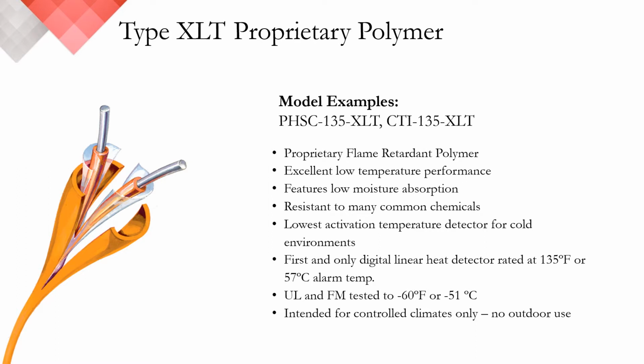While we do offer other products with some well-known industry jacketing materials, such as a PVC or a fluoropolymer, our XLT jackets are manufactured with a proprietary outer jacket material that is extremely soft and pliable. This design feature assures survivability at very low temperatures, as this detector type is UL listed and FM approved to minus 60 degrees Fahrenheit or minus 51 Celsius. This detector was designed exclusively for use in refrigerated and freezer warehousing and is not intended for outdoor use.